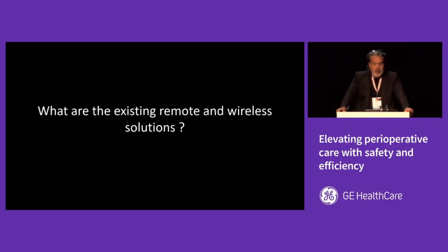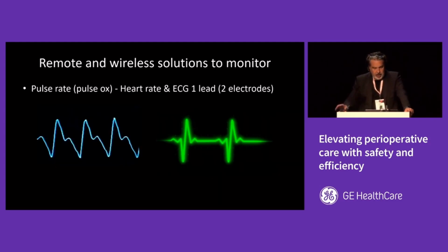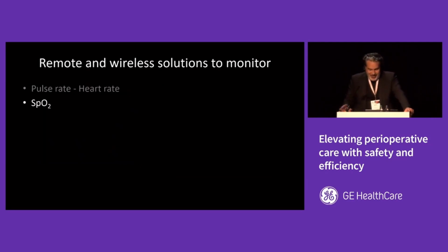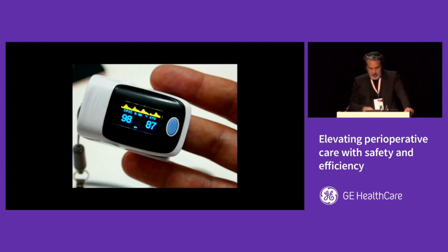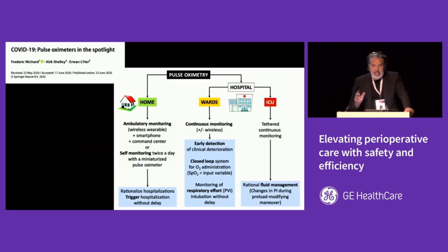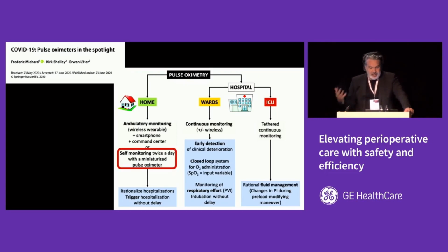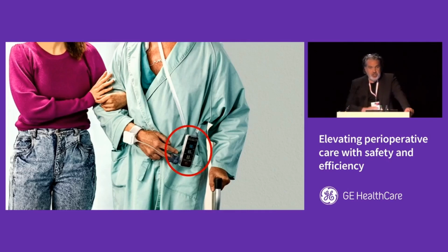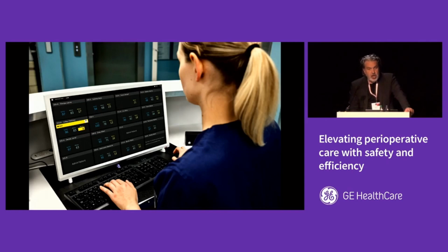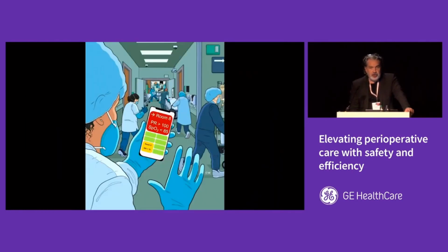What are now the existing remote and wireless solutions? So clearly to monitor pulse rate, it's not a big deal. You need a pulse oximeter. To monitor heart rate, or ECG, one lead, you need 2 skin electrodes, which are today very often combined in the same sensor. To monitor SpO2, you need a pulse oximeter. There are miniaturized pulse oximeters now available. They have been increasingly used during the COVID-19 pandemic, mainly for self-monitoring, but we could use them as well for continuous monitoring on hospital wards, provided, of course, they are used in combination with a gateway that will continuously transmit the information to the central station or directly to the pager or the smartphone of the nurse.